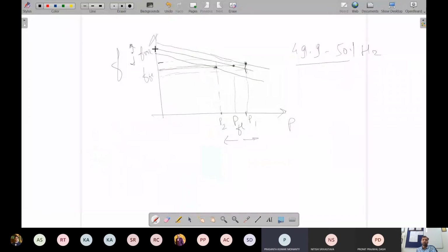So that is how it is done. What you want is that your no load speed should increase or decrease. Basically, your turbine speed will increase or decrease. And how will turbine speed increase? The flow of the fuel will be regulated, increased or decreased. When we talk about a hydro turbine, it is the opening of the wicket gates, or if you talk about the Pelton turbine, the opening of the nozzle through which the water is impinged on the turbine, that will be varied. It's as simple as that. Basically the mechanical movement of the wicket gates, or the opening of the nozzles, is what will be monitored.